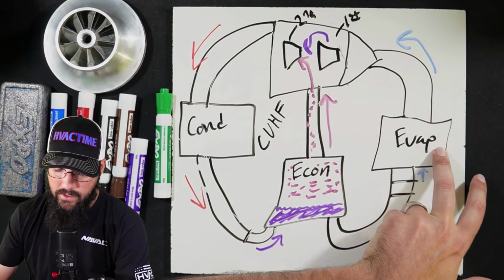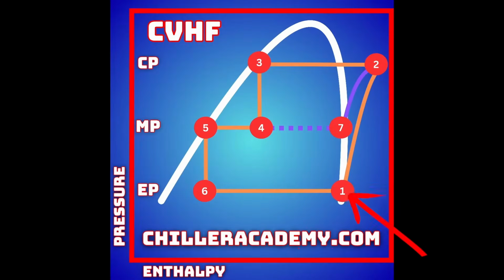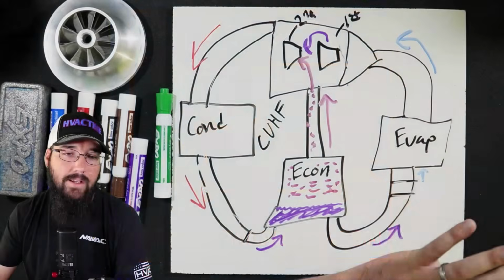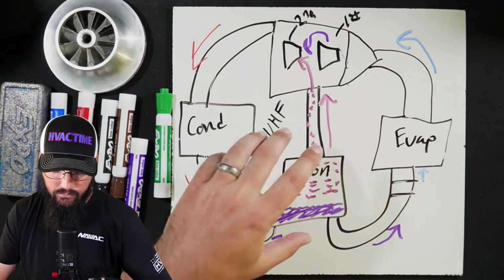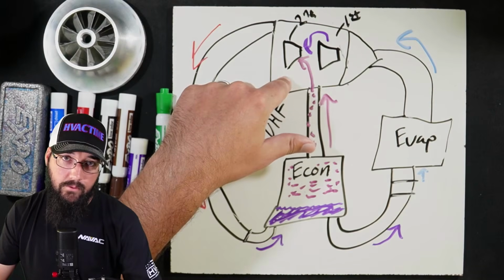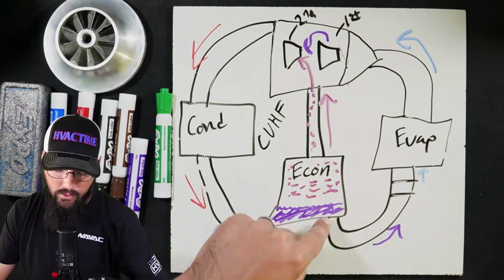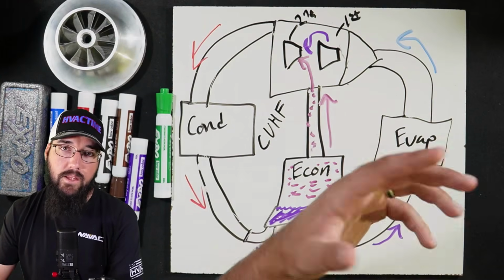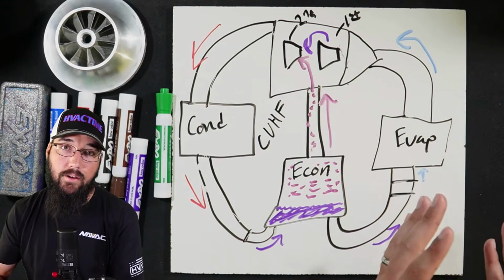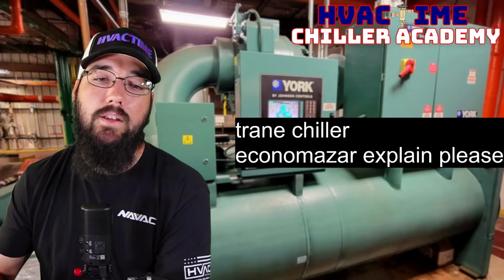So as we come through this line, we are now into this 6 to 1 stage, which is our superheating stage. So we're going from a saturated liquid refrigerant, low pressure, or at evaporator pressure, and we're flowing up to our point 1, which is back to our suction line coming into the compressor once we hit this point. And the whole cycle starts over again. So this is the second part of what the economizer is doing inside of a Trane compressor, or in a Trane CVH refrigerant circuit. It reduces compressor load by recycling some of that medium pressure vapor, but also improves our enthalpy going into the evaporator, giving us better heat content. These two things together make a very effective machine. So that is the basic process of a Trane water-cooled centrifugal with the economizer.